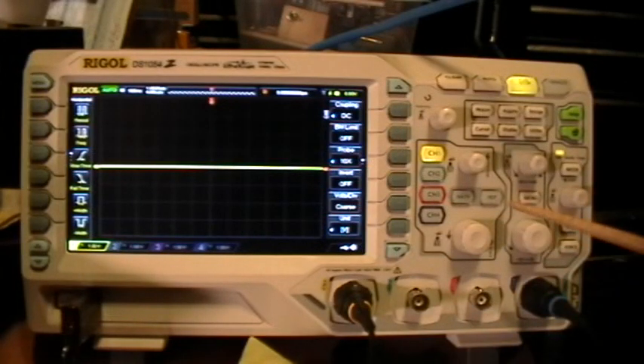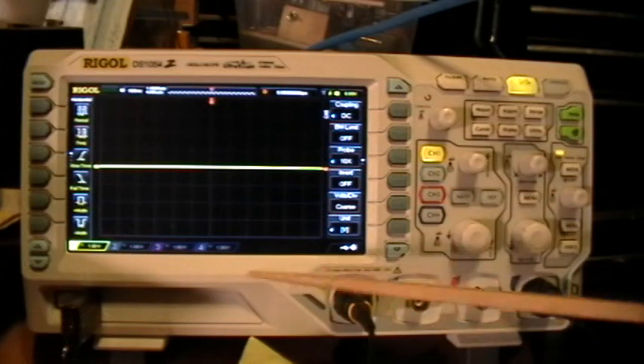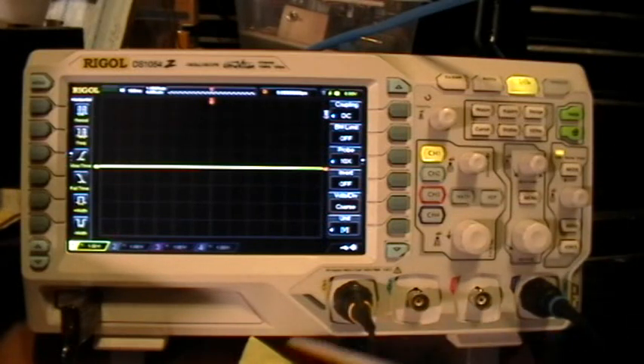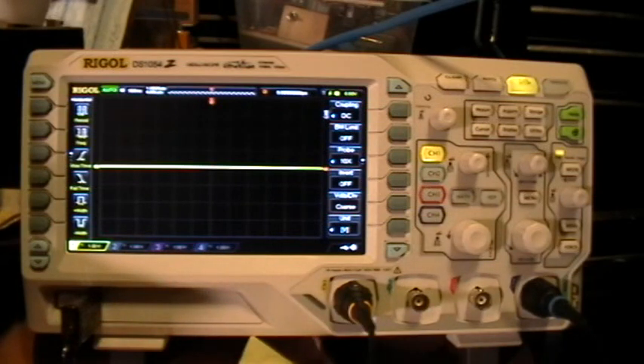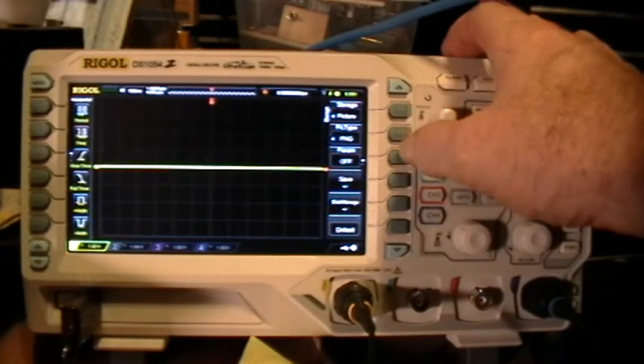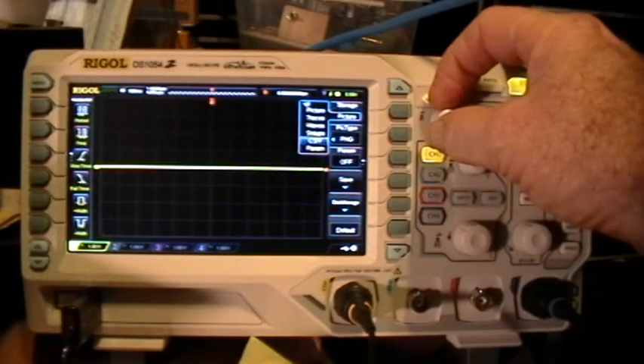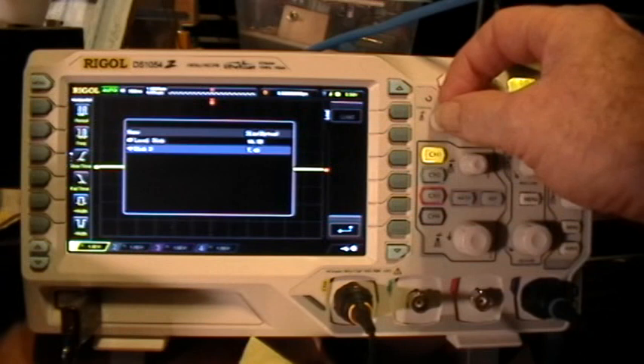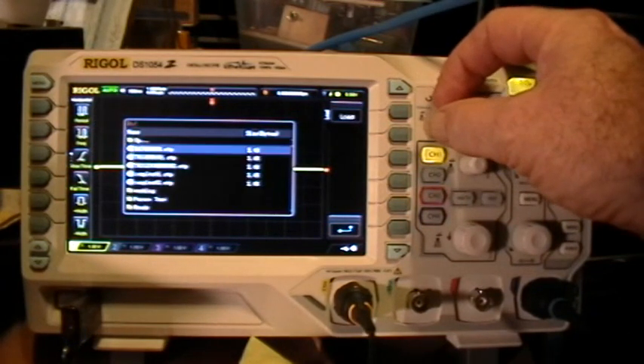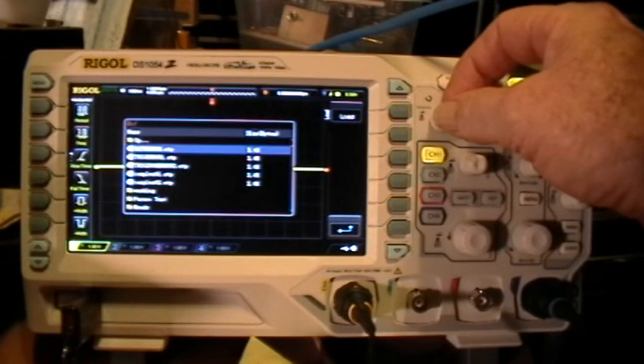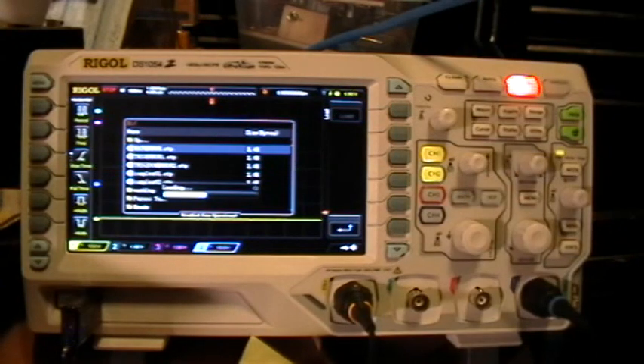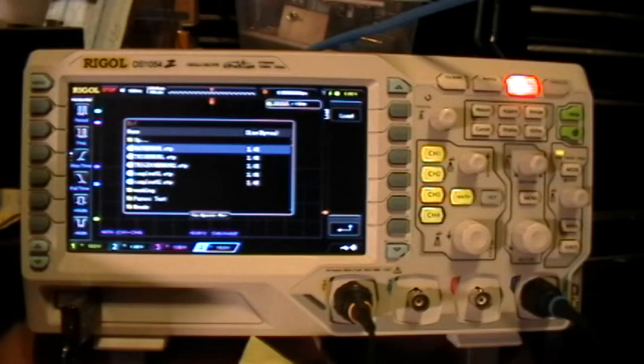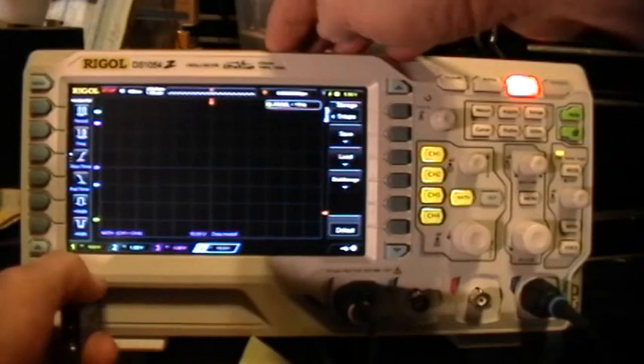So now we'll test for the math error bug. I've got a couple of probes hooked up and these are going to a voltage controlled oscillator that I'll turn on in a moment. And I've put a USB stick in there that has the setup file to reproduce the math bug. So let's go to storage, storage type setups, load from the external disk, math error setup, and load.